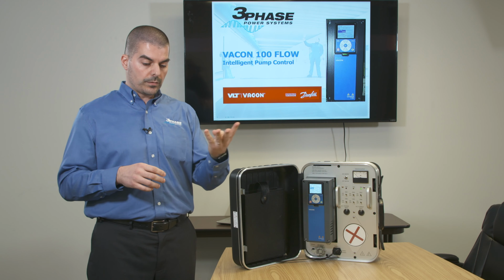We want to know if the drive is asleep. We want to know if the drive can soft fill our pipes. It actually tells you directly on the screen the status of the PID loop. Then we can also display the motor current as well. In this case, the DC link voltage is going to tell us information about the input voltage, which is fantastic. We can also monitor the digital inputs. If we have any selector switches, we can actually monitor their status if they're off or on. This is displayed in this position on the bottom left.